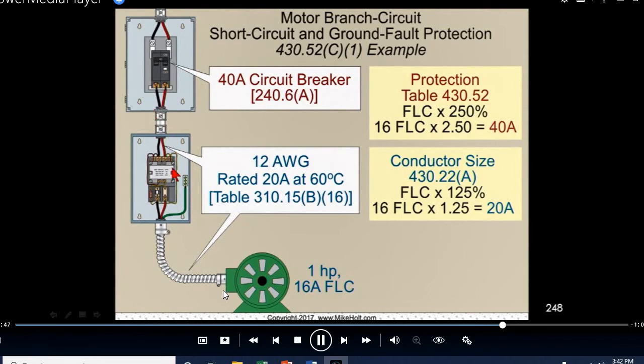And listen, guys, we put 12 gauge wire here. Think about that. If you short two 12 gauge wires, you're lucky to trip the 40 amp breaker. You're hoping you don't take the 200 amp breaker in the house. How many guys have ever tripped a much larger breaker on an individual branch circuit? I'll tell you a story. I'll get back to this story, but let me tell you another story.